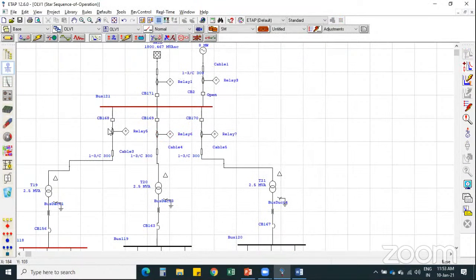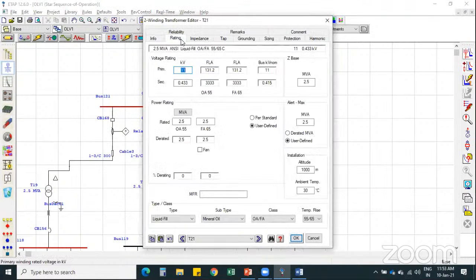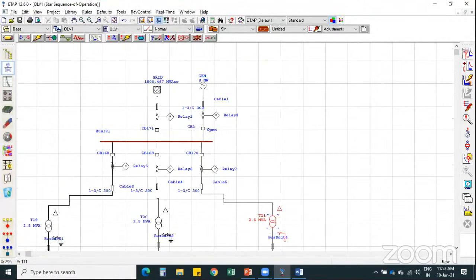Okay, now with this we need to set this feeder such that the summation of these three transformers is considered. The full load ampere of one transformer is 131 ampere. So for three transformers, cumulative or summation, it is around 393 ampere. The sum of all three transformers is 393.6 ampere.